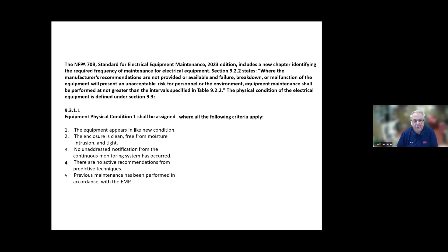So that's condition one, like new conditions. Condition two is pretty much almost every other building we've seen in Boston - it has some sort of maintenance program, has been shut down for de-energized maintenance before, and there's some awareness of what problems may exist while actively trying to keep up to par. The actual chart will tell you the exact frequencies, but this is pretty much every building I've walked into - it's rare to see anything beyond this. Condition three I've seen a handful of times, but condition three is walking into a mess.